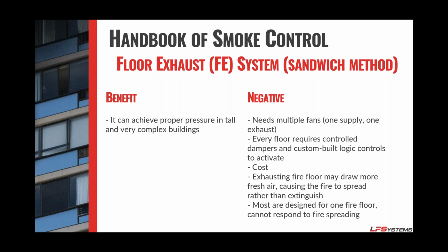If you exhaust the fire floor, it actually can draw fresh air in. Again, if you're pulling air out of a space, it's going to want to be replaced with fresh air. So when there's a fire floor drawing air out, you assume that the door to the stairwell will be open, so it'll naturally draw more air in to that fire floor, which could actually help spread the fire rather than extinguish it. And then the other thing is most sandwich method systems are designed for one fire floor. If that fire spreads, the system just doesn't know how to respond. So you design the fan to exhaust 2 to 3 floors. If you get into 4, 5, 6 floors now with multiple fire floors, again, it starts to fail.